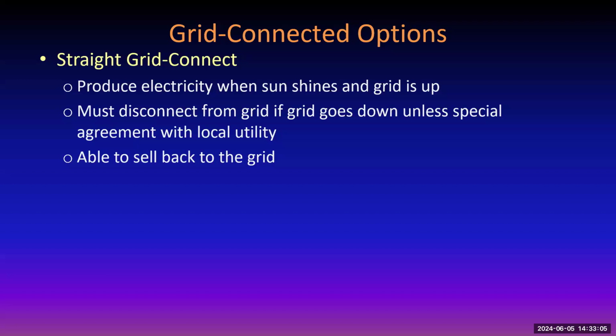So it makes electricity when the sun shines and the grid is connected. It sends electricity to whatever loads you want. And if there's any left over, it goes back to the grid, provided the grid is up. But if the grid goes down, then your system has to go down, because otherwise it would be sending electricity back to the grid, maybe when somebody is trying to repair a 12,000 volt distribution line. And solar electricity can make 12,000 volts backfed through a transformer just as well as any other kind of electricity, and it has the same effect on a person who inadvertently gets in contact with it. So it's pretty important.